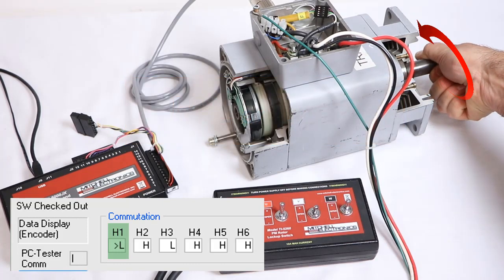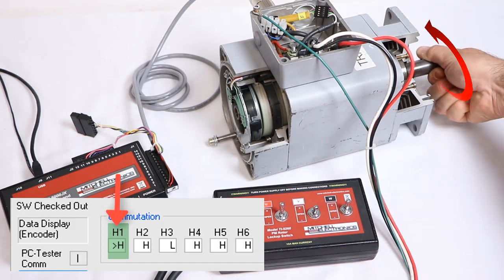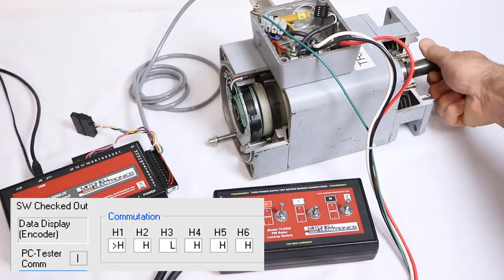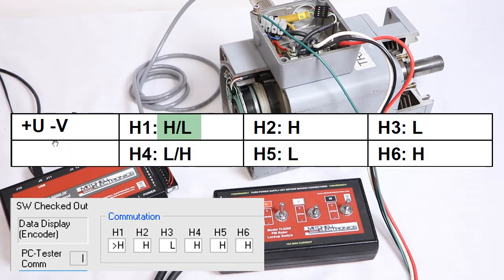Siemens motors are clockwise, and the H1 pulse is toggling from high to low in the clockwise direction. The alignment pattern is then written like this, or like this if complement lines are included.